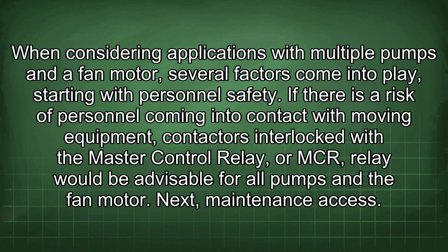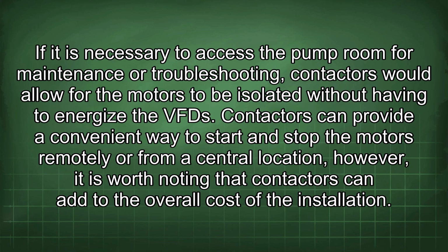When considering applications with multiple pumps and a fan motor, several factors come into play, starting with personnel safety. If there is a risk of personnel coming into contact with moving equipment, contactors interlocked with the Master Control Relay, or MCR, relay would be advisable for all pumps and the fan motor. Next, maintenance access. If it is necessary to access the pump room for maintenance or troubleshooting, contactors would allow for the motors to be isolated without having to energize the VFD. Contactors can provide a convenient way to start and stop the motors remotely or from a central location. However, it is worth noting that contactors can add to the overall cost of the installation.